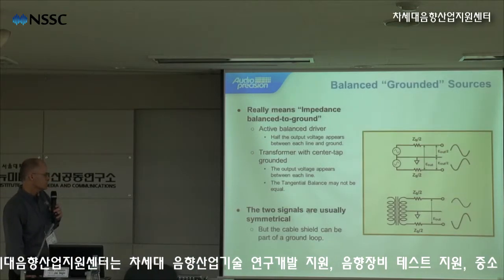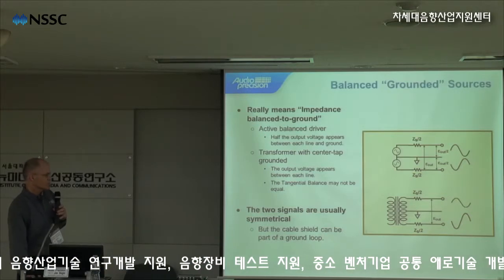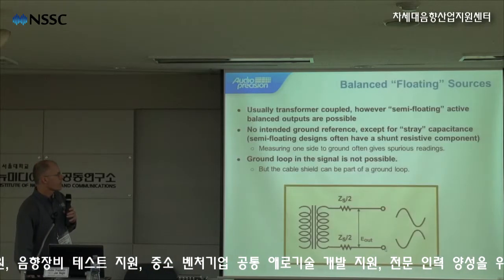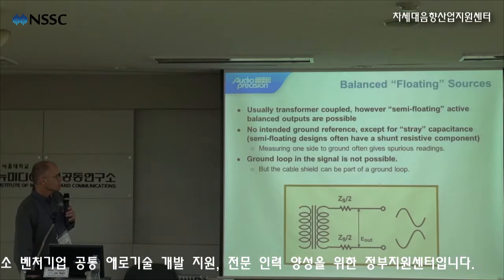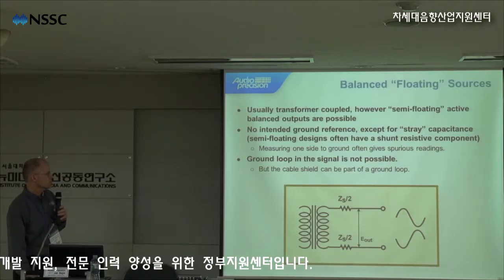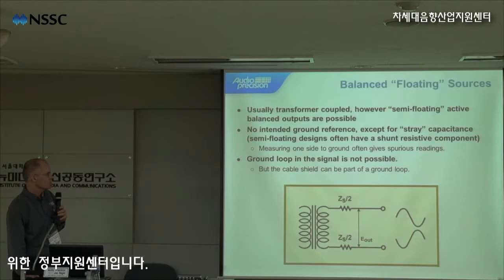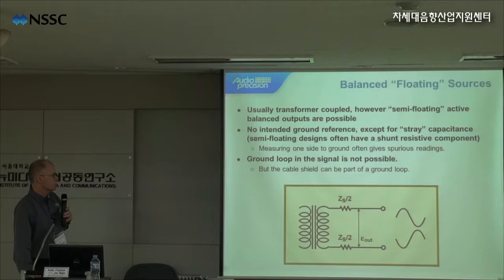The two signals are usually symmetrical, but the cable shield can be a part of a ground loop. Balanced floating sources are usually transformer coupled. However, semi-floating active balance outputs are also possible. There's no intended ground reference except for the stray capacitance. Semi-floating designs often have a shunt resistive component, so measuring from one side to ground often gives spurious readings. A ground loop in the signal is not possible, but the cable shield can be part of a ground loop.